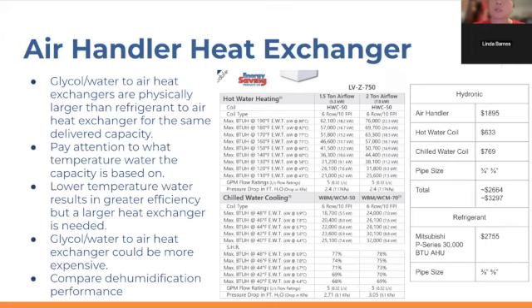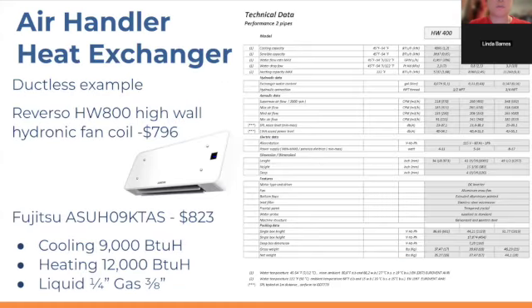So that's why there's some manufacturers, like the one I'm showing here, that give you the choice of what chilled water coil to insert and what hot water coil to insert, and you can mix and match in order to meet the heating cooling load of your particular climate zone. That's kind of smart. Now, refrigerant coils, like I said, you can fill a coil with a different amount of refrigerant through software, and then adjust your superheat target and subcool targets in order to have the same effect. Now, on a ductless example, again, price difference.